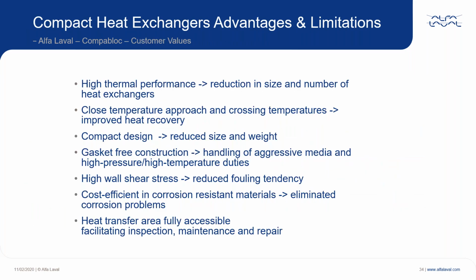Again, the advantage is they've got a high thermal performance. So you can have a reduction in size and the number of heat exchangers. We can have a close temperature approach and crossing temperatures. They are a compact design, they're gasket free. And because of the high wall shear stresses, there's a reduced fouling tendency. And because the wetted area is small, we can use non-corrosive materials.